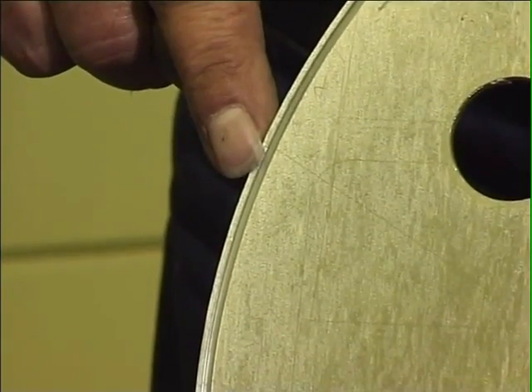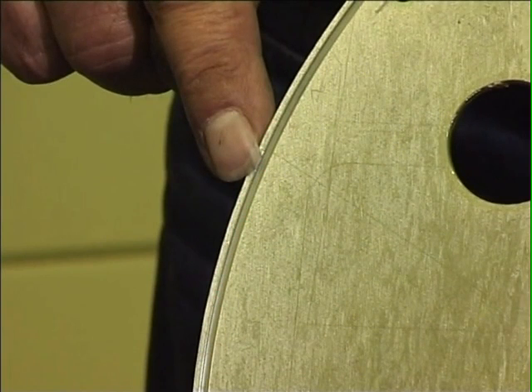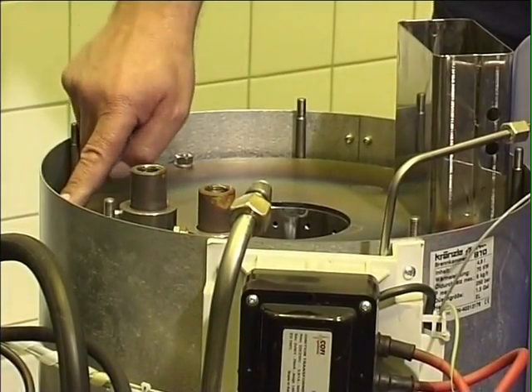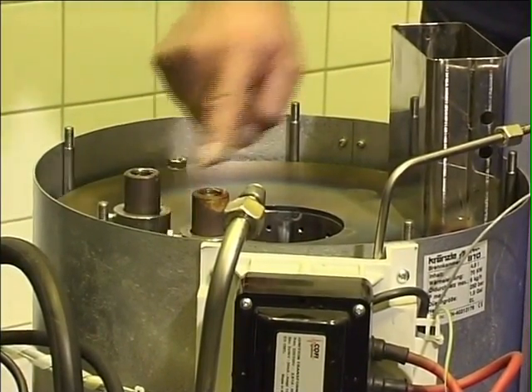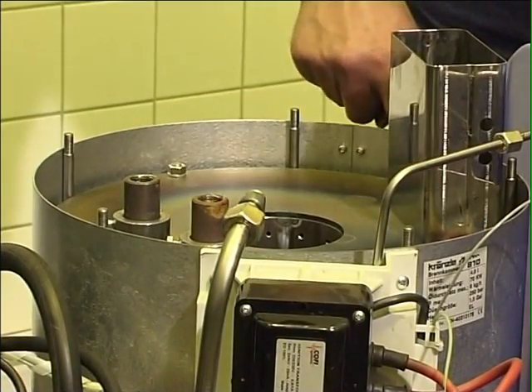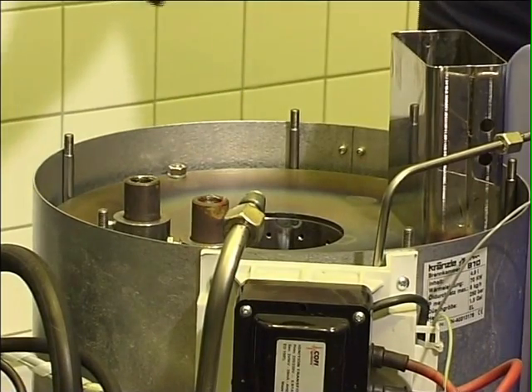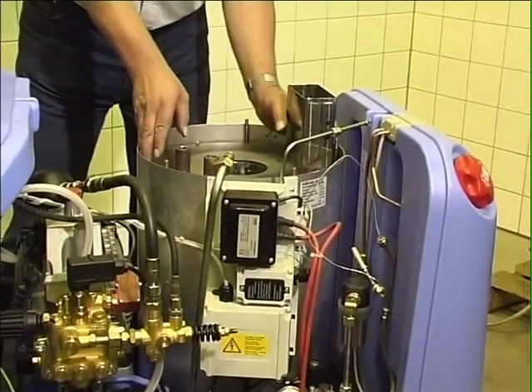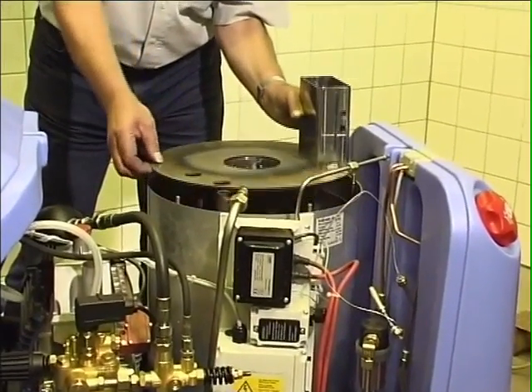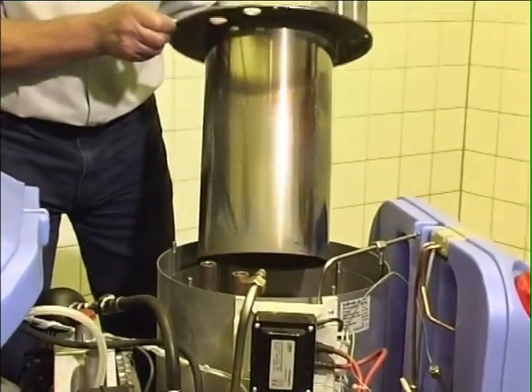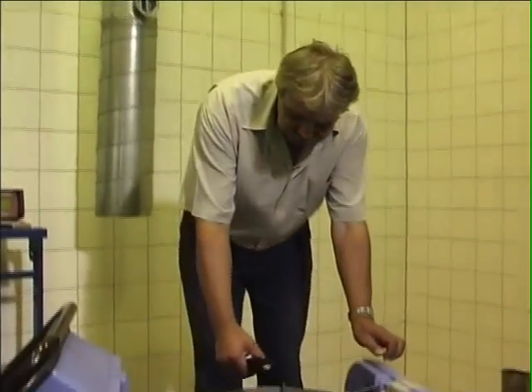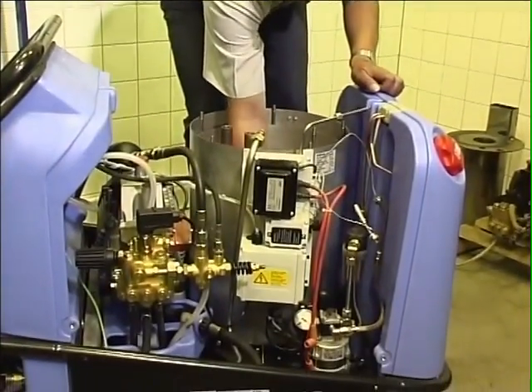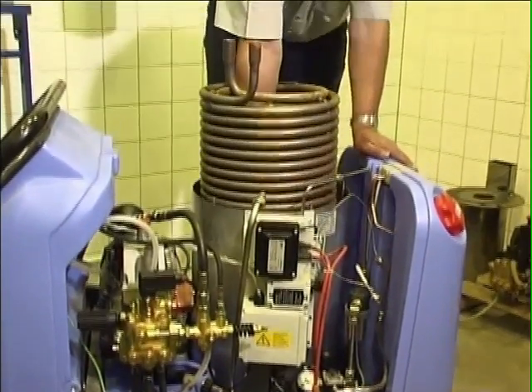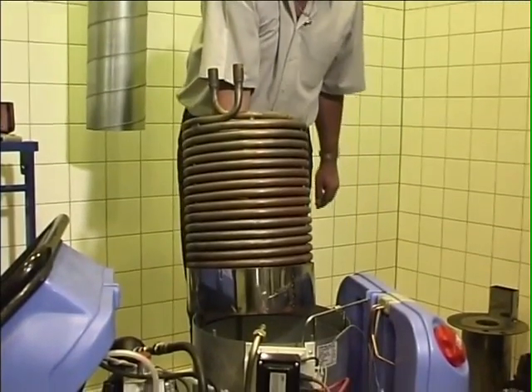This is a special feature with Kranzle high pressure cleaners. It makes sure that the flame is in the middle of the combustion chamber and thus in the optimum position when installing and even later. The inlay of the heating coil can also be easily removed after the screws have been loosened. By the way, the wound heating coil is 34 meters long and can hold 5 liters of water. With a 25 centimeter long flat iron that you clamp between the coils, you can easily pull the heating coil upward.